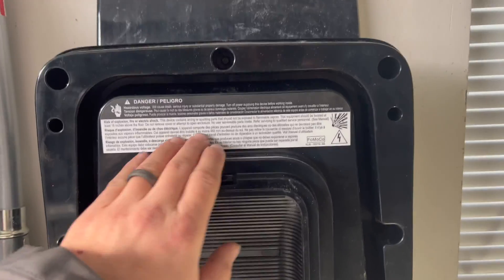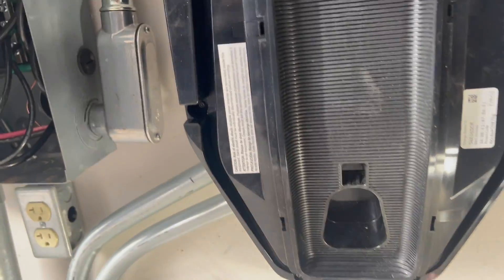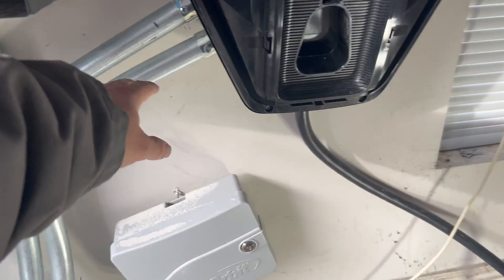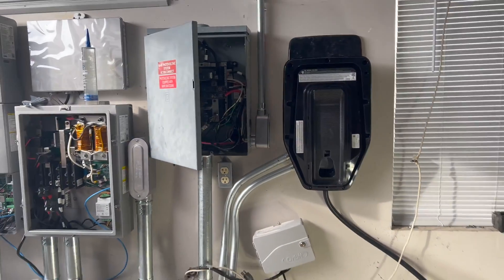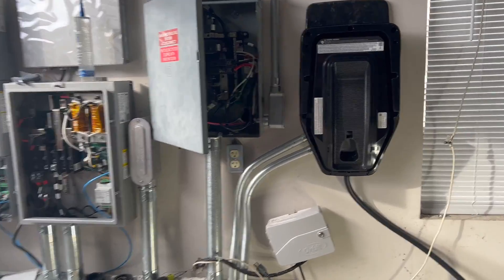The bi-directional inverter is going to go to the backup panel. The truck charger goes to the main panel AC and goes DC to the inverter, and then the inverter goes AC to the actual backup panel. Now in between the backup panel and the main panel is the MID — the Microgrid Interconnect Device. I would describe this device as intercepting some of the circuits that will be located in the backup panel.